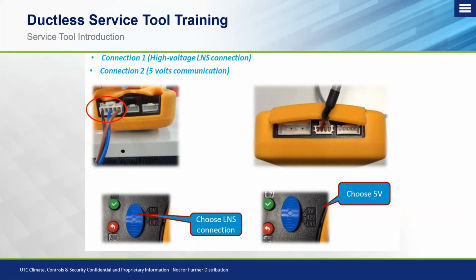Okay, do not connect these at the same time. Otherwise, you're mixing DC voltage with AC voltage in the same terminal. It's going to cause an issue and take out the tool. Okay, so before you turn power on, you're either going to choose between connection 1 or connection 2, depending on what information you're trying to access. And we'll get into that in a second on what different connections offer as far as data.